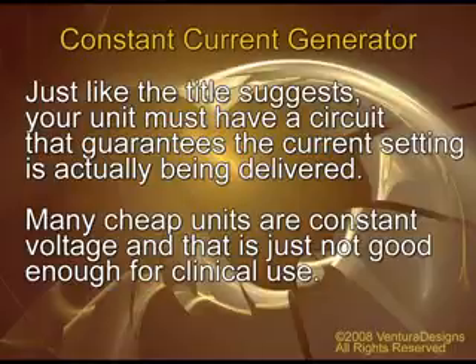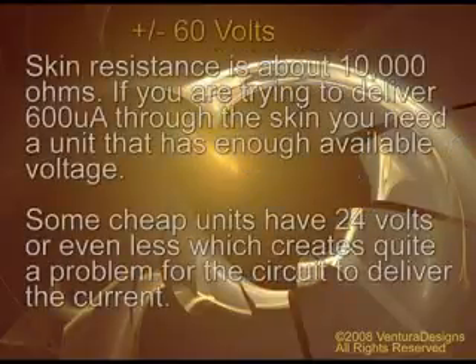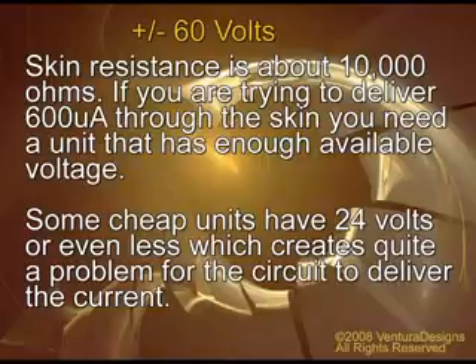It must be a constant current generator. Just like the title suggests, your unit must have a circuit that guarantees the current setting is actually being delivered. Many cheap units are constant voltage, and that is just not good enough for clinical use. The unit must have plus or minus 60 volts. Skin resistance is about 10,000 ohms. If you are trying to deliver 600 microamps through the skin, you need a unit that has enough available voltage. Some cheap units have 24 volts or even less, which creates quite a problem for the circuit to deliver the desired current.